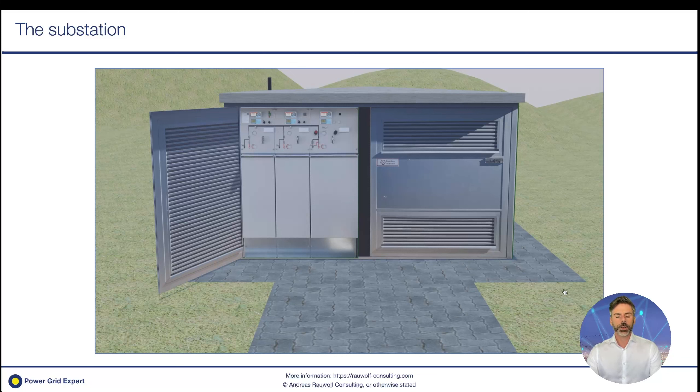In the digital substation, we have much more measurement units, control, remote control functions, RTUs (remote terminal units), modems, and so on. All these devices are connected normally to the SCADA system. To have this communication properly, there are different communication protocols which are in use here. Some of them are unique for the utility market, others are not, and we will have a look at all of them.